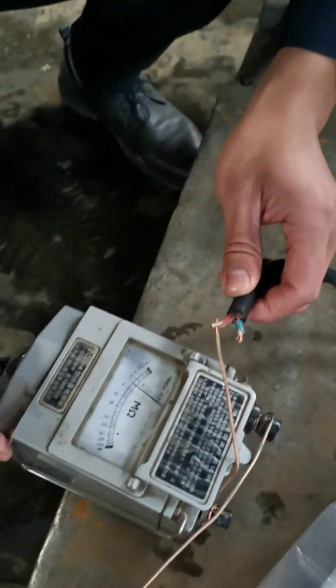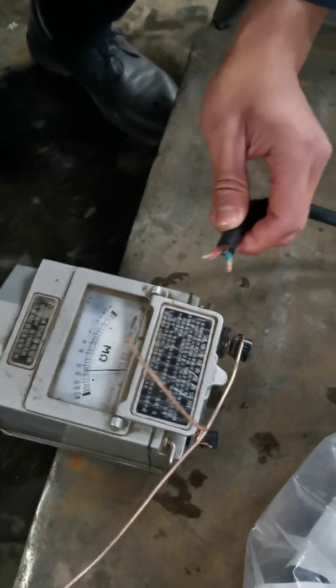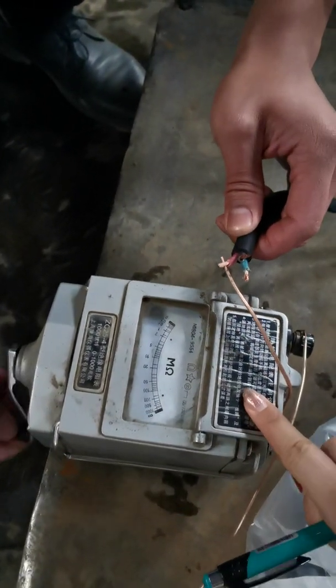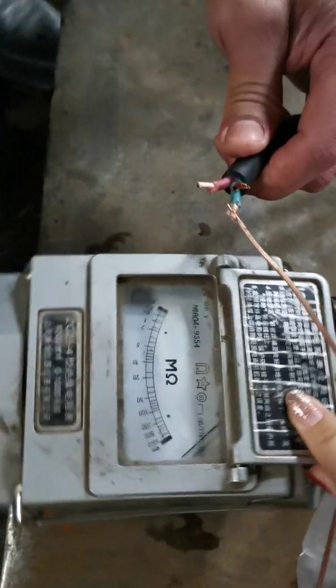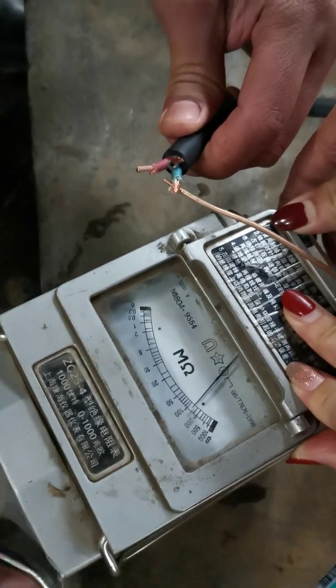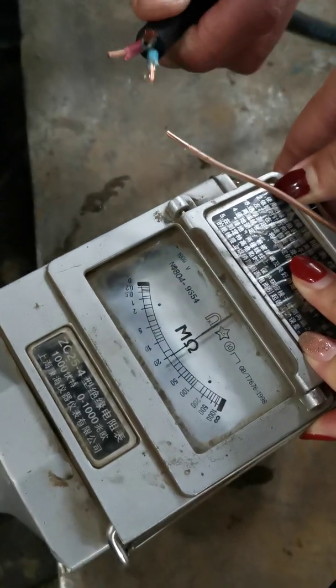The whole cable is 50 meters with no joints between all the cables. Now our engineer does the insulation test. This is the megohmmeter. Using the megohmmeter to test the insulation — you can see the insulation is good.